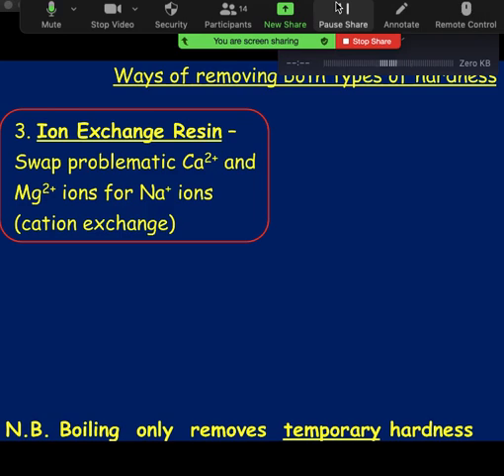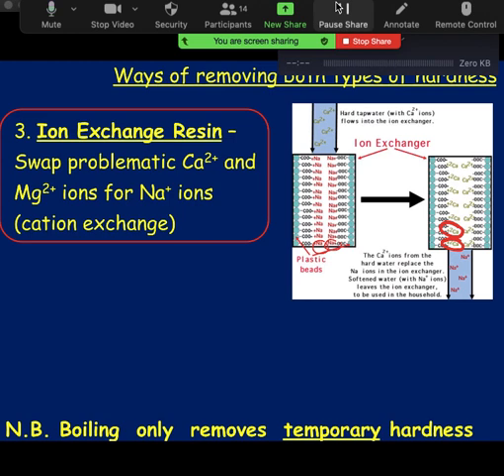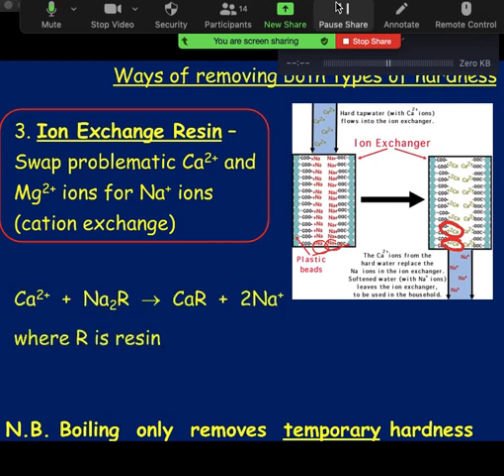For ion exchange, the resin has sodium ions in it, and literally when you pour your water through it, it swaps the calcium and magnesium out and puts the sodium ions back into the water — that's what makes it soft. These are all the sodium ions in your resin; you pass your sample through and they literally swap places. Eventually your resin will stop working because the calcium will have filled it all up. The R in the formula stands for resin — calcium ions come in to your resin, the calcium ions stay on the resin, and your sodium now leaves.